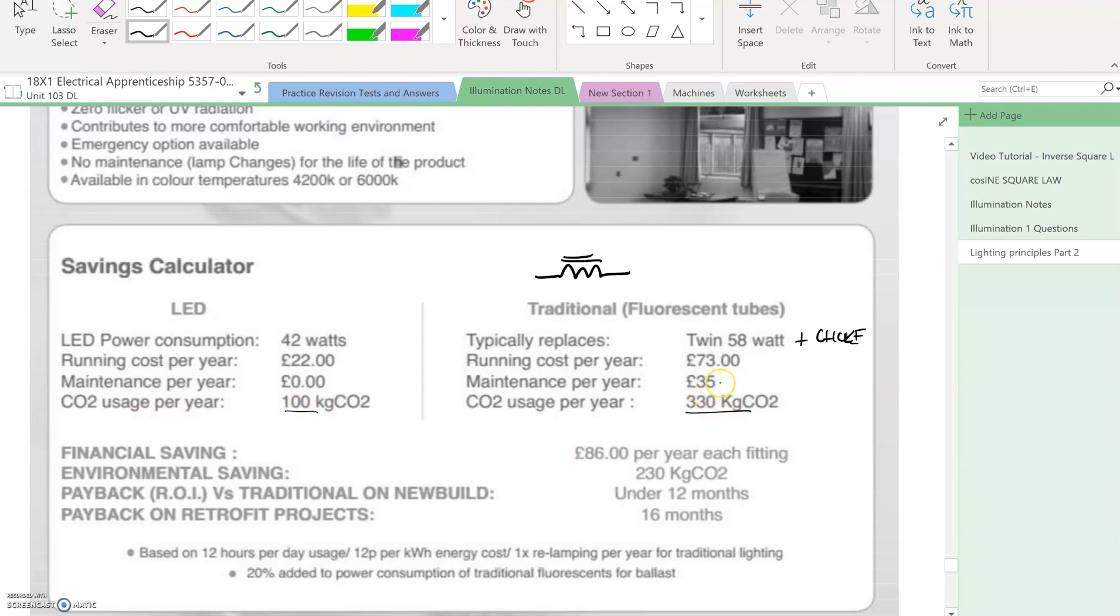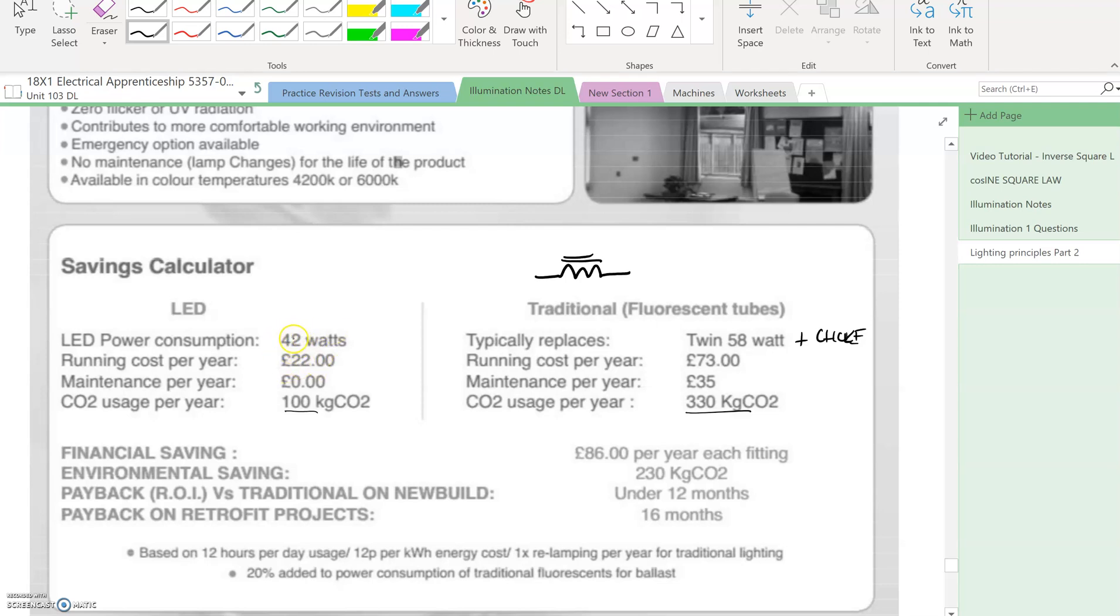Overall you can see CO2 usage per year is 100 kilograms for LED versus 330 for fluorescent. Maintenance costs per year are £0 for LED versus £35 for fluorescent, which includes starters and changing tubes. With LED, once you've fitted them away they go, no problem. Consumption is 42 watts, not significant but lower, with less maintenance costs, less CO2, and generally a much crisper light.